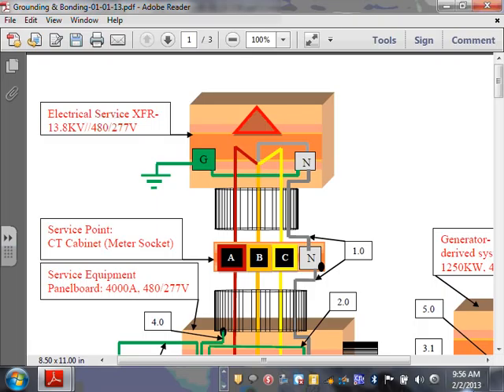We don't use 2400 volt. We take the 4160 into the primary of a delta transformer, transfer it back at the 13th floor of the hospital, right? Take it all the way to the 13th floor, transfer it down to 4160, 480, 277, and we feed all the chillers and the air handling units and cooling towers and so forth. Okay, any comments, guys, about this?